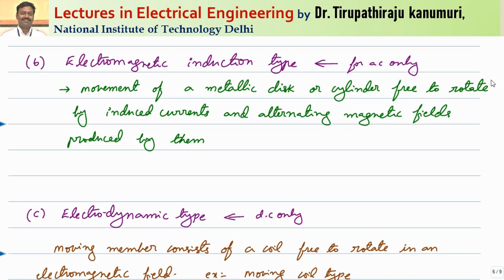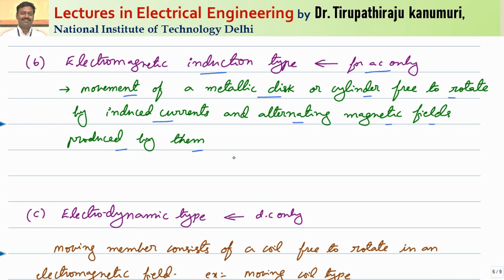The next one is electromagnetic induction type. As the name suggests, it is based on the induction principle, which can only occur with alternating current or alternating flux. That is why this can be used only for AC. In this case, the movement of a metallic disc or cylinder, free to rotate, is caused by induced currents and an alternating magnetic field — similar to your energy meter used in households.